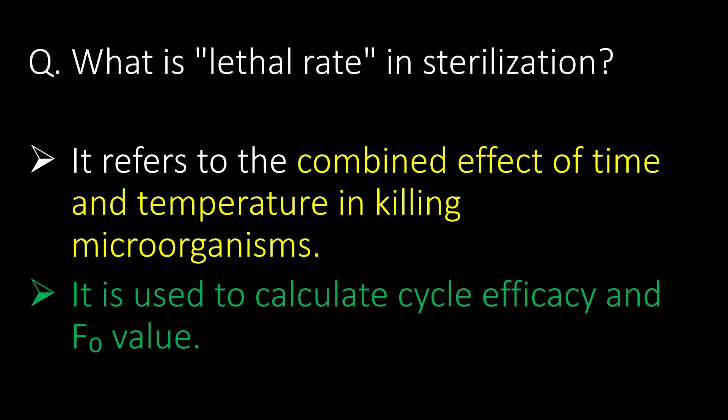What is lethal rate in sterilization? It refers to the combined effect of time and temperature in killing microorganisms. It is used to calculate cycle efficacy and F0 value.